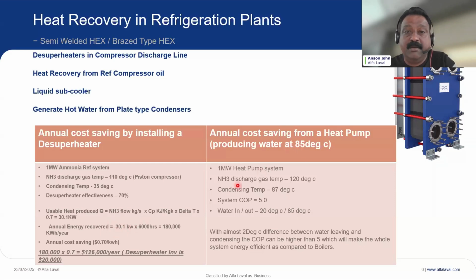And if you have annual cost saving from a heat pump, if you've got an existing industrial refrigeration plant, and by adding a condenser, if you've got a piston compressor there, the ammonia discharge gas temperature can be up to 120. Even we are designing for 150 degrees C, as I said, and you can set the condensing temperature of 87, which will help the customer to heat up the water from 20 to 85 degrees C. And with a very close temperature of like 2 degrees C difference between the water leaving and the condensing, the system COP can be 5 almost or higher, and that will bring a lot of savings.